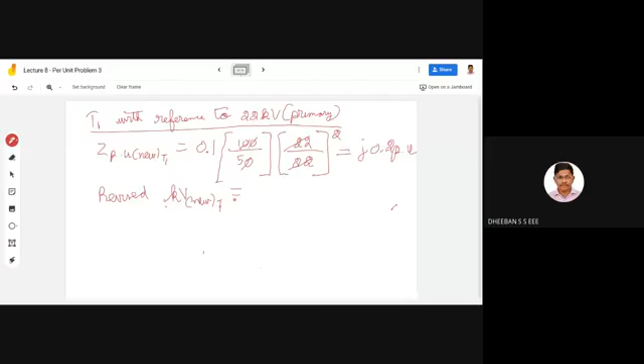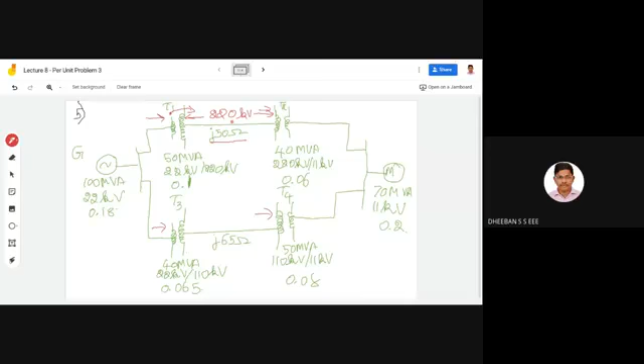So this is your revised voltage, and this revised voltage is the voltage drop which is across the secondary of your T1, to the primary of your T2. So the transmission line impedance will use the revised voltage of 220 kV. So this is with respect to your T1.